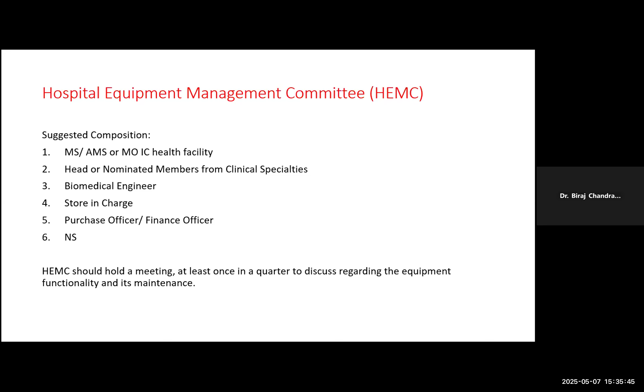What will the committee do? It receives proposals and evaluates them with justification. When there is a demand for any equipment or medical device, it should check whether proper justification is there or not. They will do the need analysis and cost benefit analysis of the equipment. Then receipt, installation and commissioning of the new equipment. So whether the equipment is being installed as per instruction, whether calibration is done and everything is in place, all requirements are being fulfilled. Then training of the staff who will be operating the equipment.